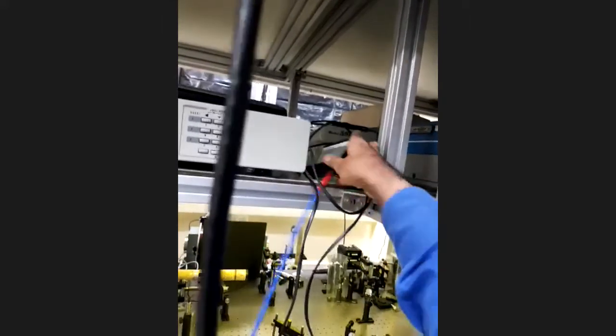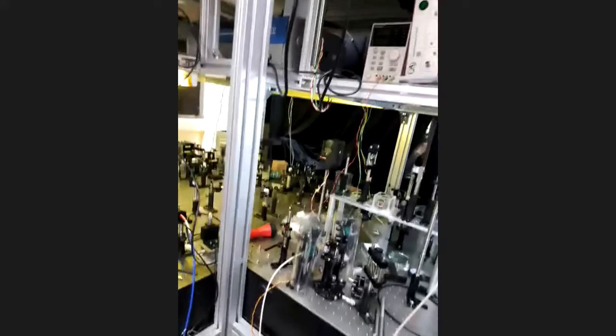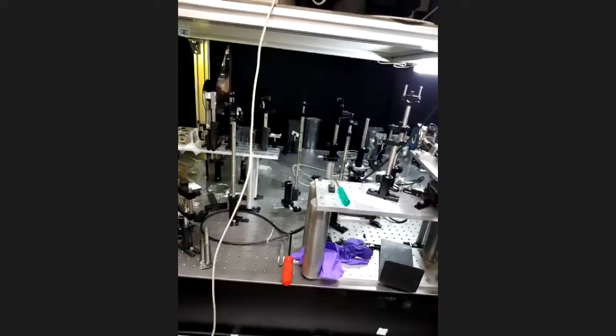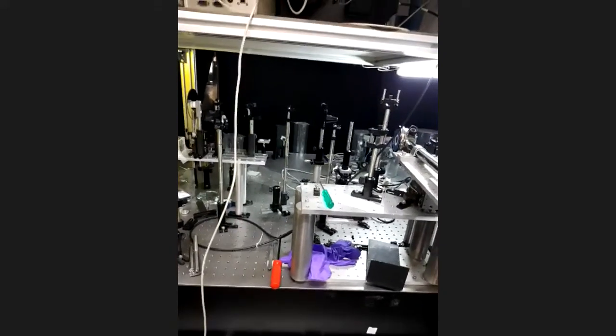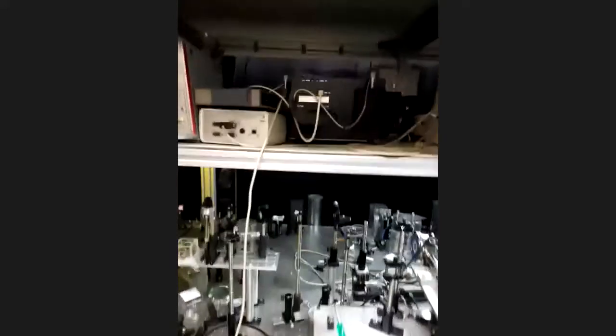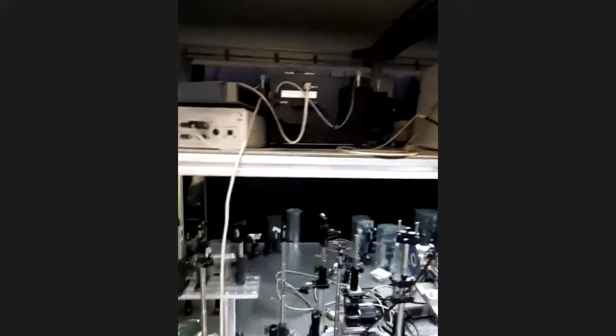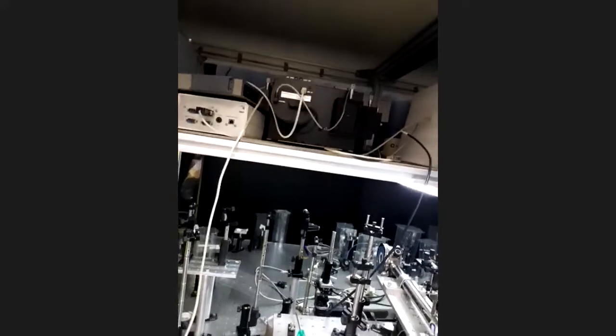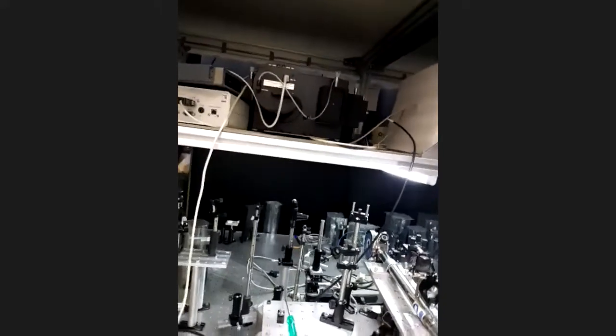The difference between these two, the small one and the big one, is the resolution. So how precisely you can find the wavelength of the light which is incident on it, and how can you resolve two different colors or two different wavelengths which are falling on the spectrometer. Okay. So a half-meter one gives us a resolution of 0.1 nanometer. Right? It can go even smaller depending on the grating which we use.